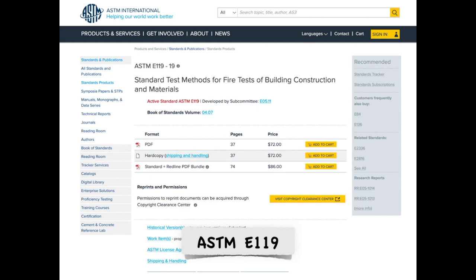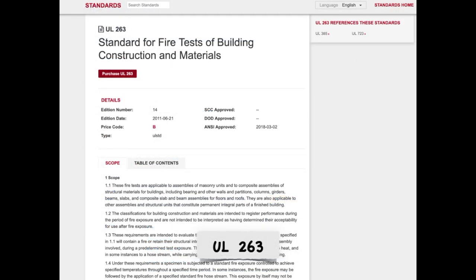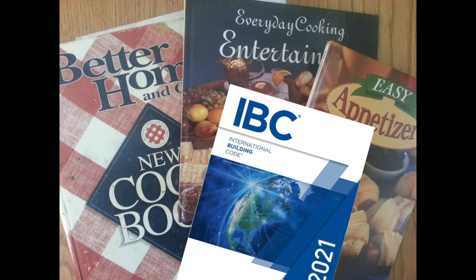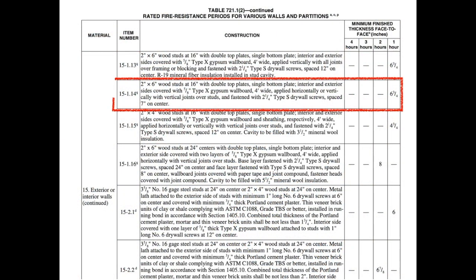That rating has to be tested and proven through either ASTM E-119 or UL 263. These tests allow for proprietary products and unique assemblies for fire protection to be proven and made available for the market. But you can also use any of the methods provided in the International Building Code, including prescriptive assemblies that are essentially just recipes for construction. Here's an example of a basic 1-hour rated wall using 5/8-inch Type X drywall — just a recipe from the IBC.